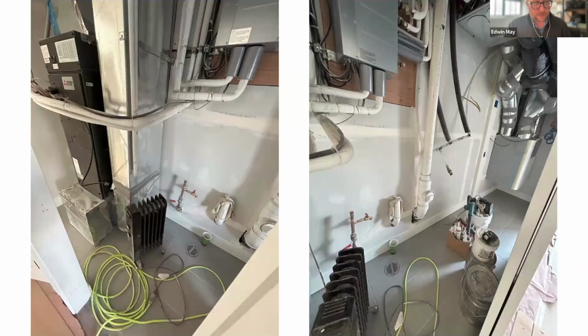For the mechanical system, we want to approach it very intentionally and thoughtfully from the beginning of the project. In general, we recommend splitting apart the heating system, the cooling system, and the ventilation system rather than having one thing called HVAC, because these systems have different logics, rules, and requirements. The fresh air ventilation system keeps people healthy, while the heating and cooling systems keep the space comfortable.